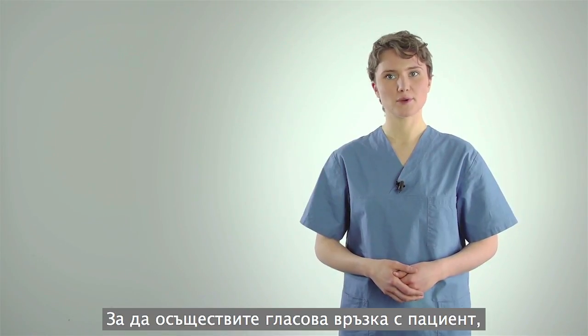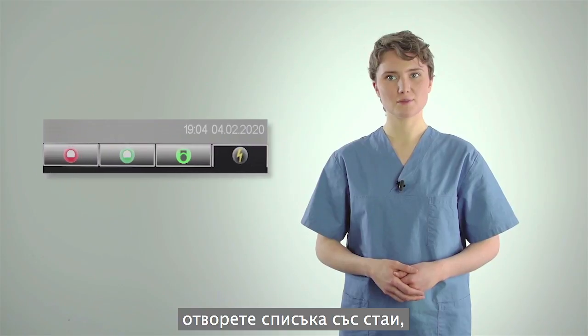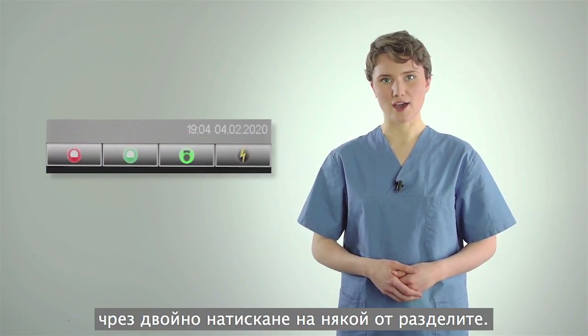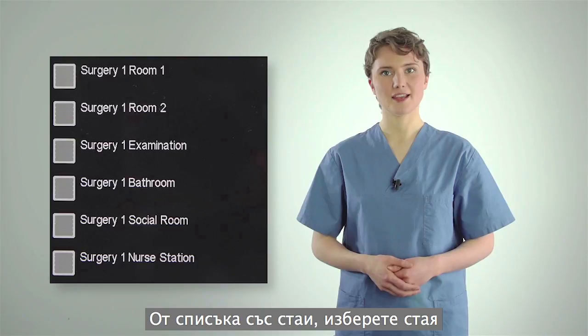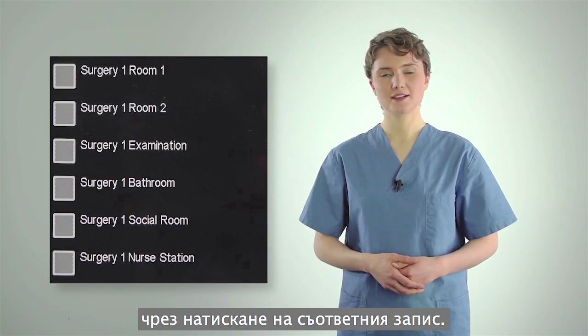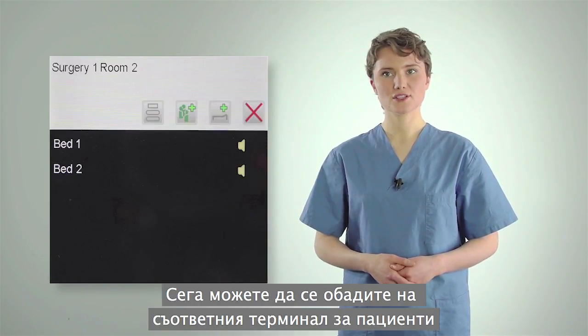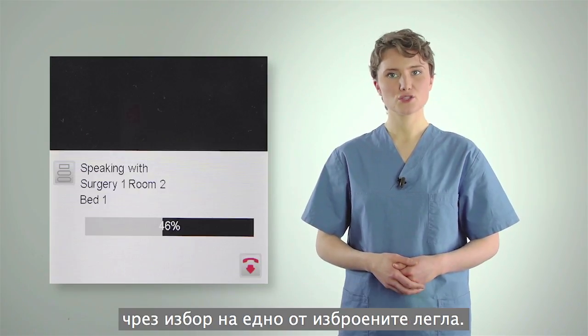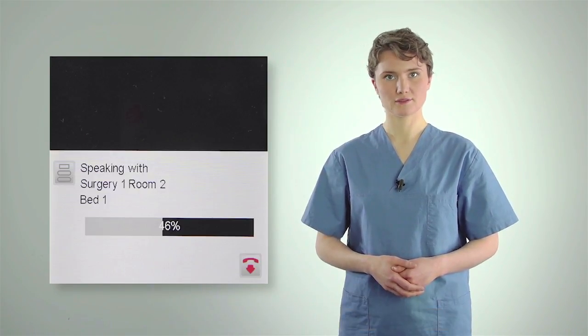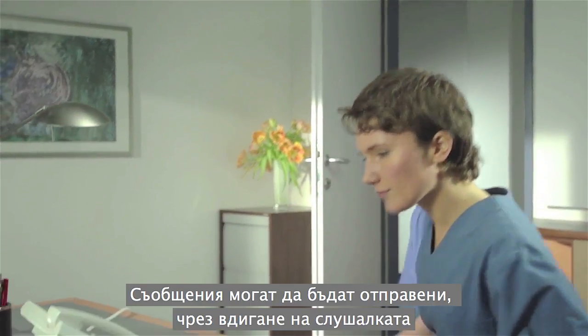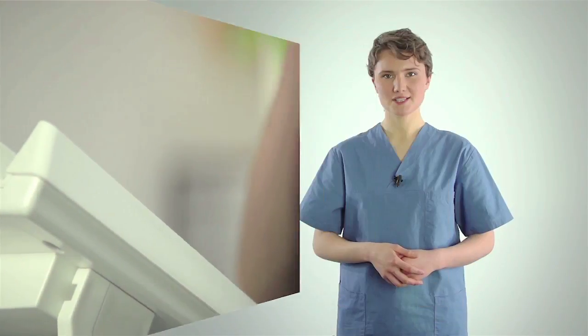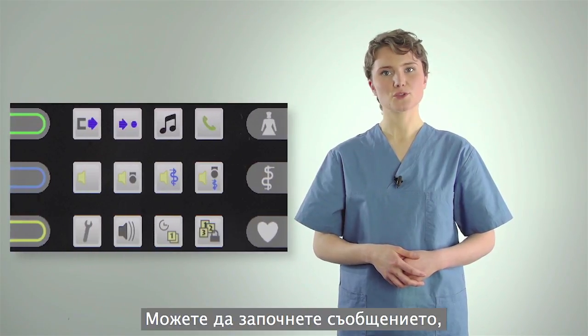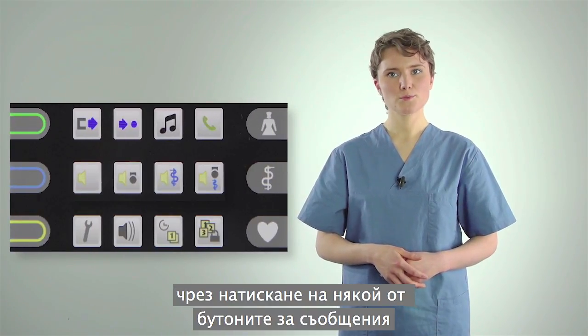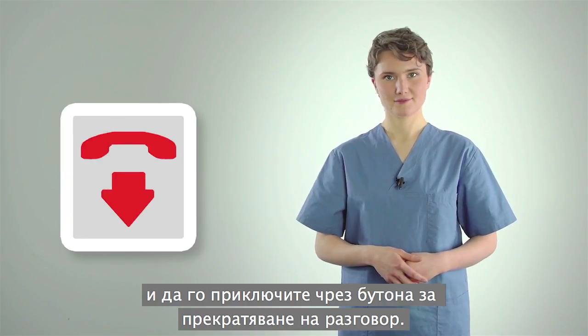To establish a voice connection to a patient, open the room list by pressing one of the tabs twice. From the list, select the room by pressing the corresponding entry. Now you can call the corresponding patient terminal by selecting one of the listed beds. Announcements can be made by lifting the handset or using the hands-free function. 4 announcement options are available. You can start your announcement by pressing one of the announcement buttons and end it via the End Call button.